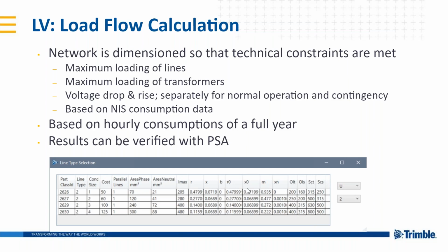We are able to handle hourly data in the load flow calculation. So with this built-in accurate enough load flow calculation, we are able to ensure that the loading of the lines, loading of the transformers is kept within the allowed limits. We make sure that the voltage drop is not more than allowed. And of course, if there's a lot of renewables injection to the grid, we are watching after the voltage rise in those cases, and the user can set the limits for those voltages for normal operation and for contingency.